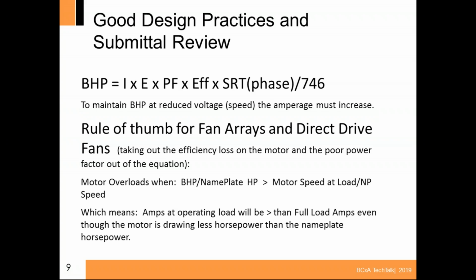Now that motor burns up, and the guy in the shop says they don't have a 1150 RPM motor, but they have a 1750 RPM motor that's 10 horsepower, okay? He thinks he can grab it off the shelf because it's 10 horsepower, put it into this fan and reconnect it, and he'll use a variable speed drive to operate it at 1150. Well, the problem is that fan requires 9 brake horsepower at 1150 RPM, or 1140. But that motor is now going to be operating at about 66% speed.